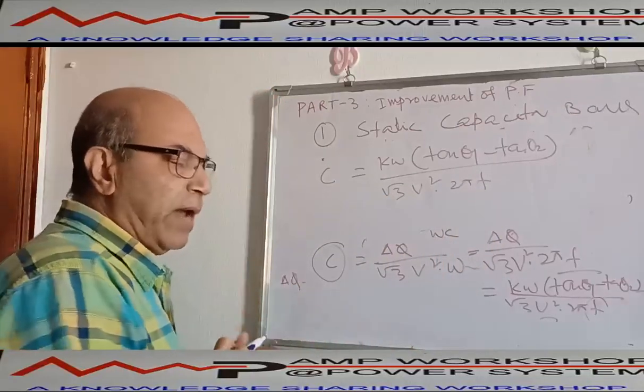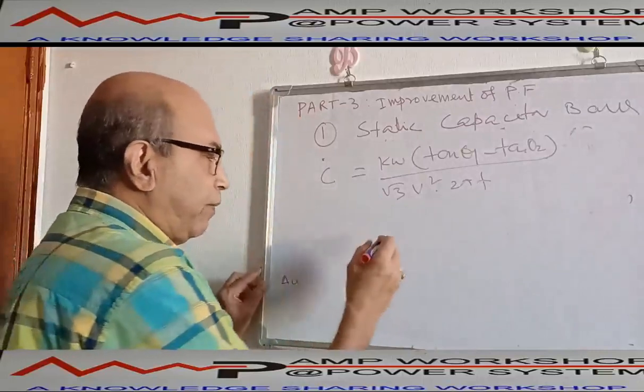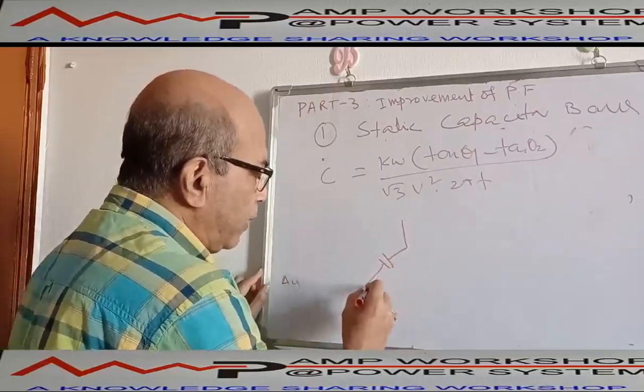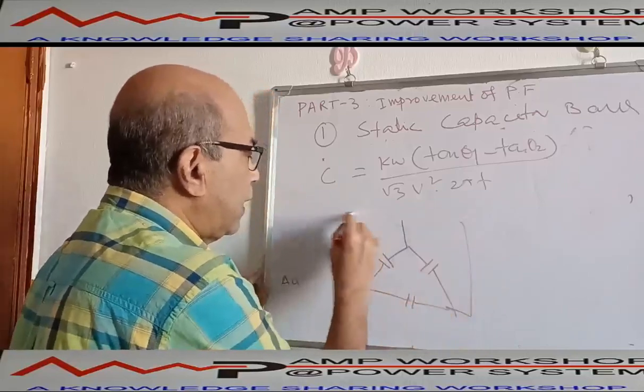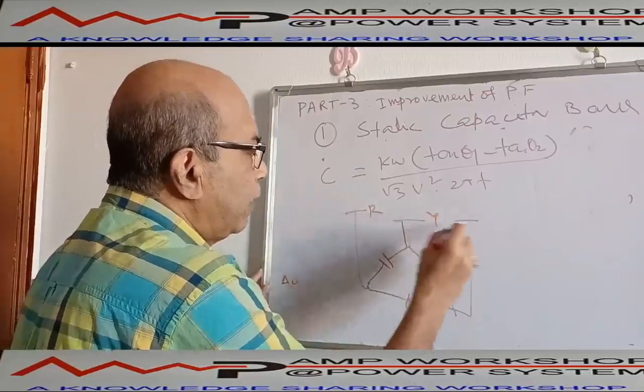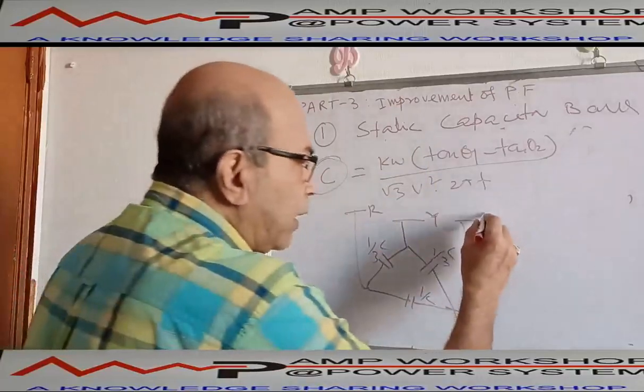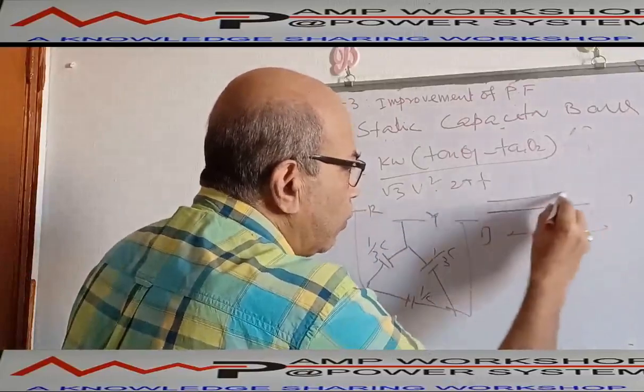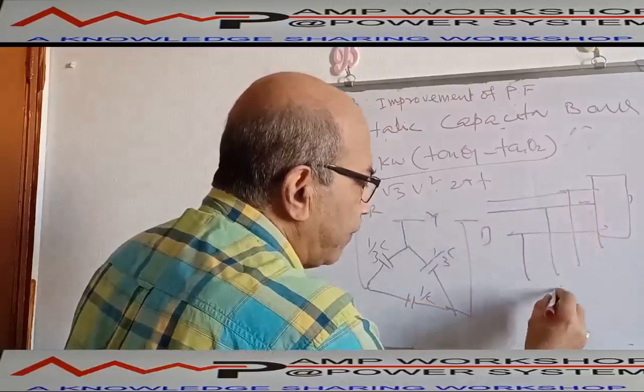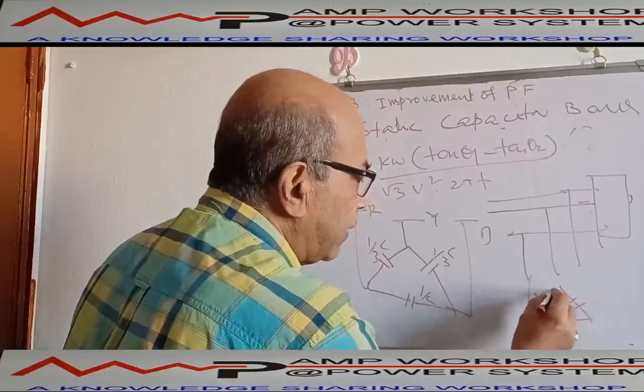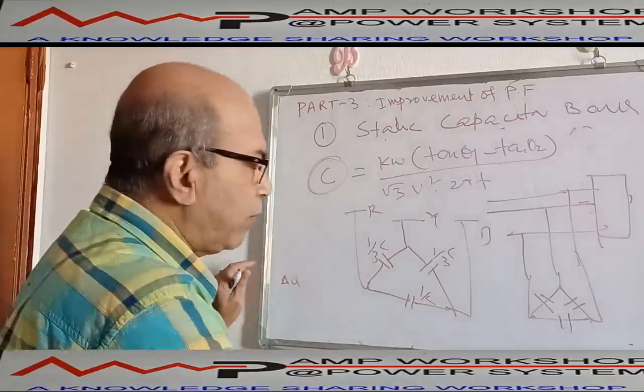So the capacitance value C equals kilowatts × (tan θ1 − tan θ2) divided by (√3 × V² × 2πF). This is the capacitance to be added to the line. For a three-phase system, we generally connect this capacitor bank in delta form — three capacitors connected in delta across the red, yellow, and blue phases. The capacitor bank is connected in parallel to the three-phase line going to the load.